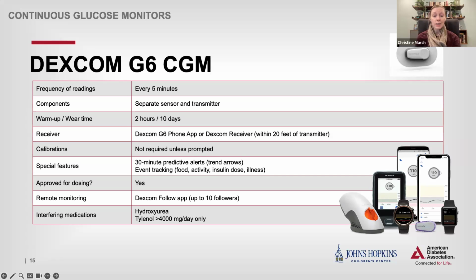Calibrations are not required for the G6; it's considered factory calibrated. When you initially put on a new sensor, there's a code the family has to enter for it to work properly. If they don't have that code for whatever reason, some initial calibration would be required. Dexcom has released documentation about calibrating this device, which is a question I frequently get. What they've shared is that calibrating the system could have a negative, positive, or no effect on accuracy, so generally it's not recommended. We'll talk about accuracy in more detail in a bit.